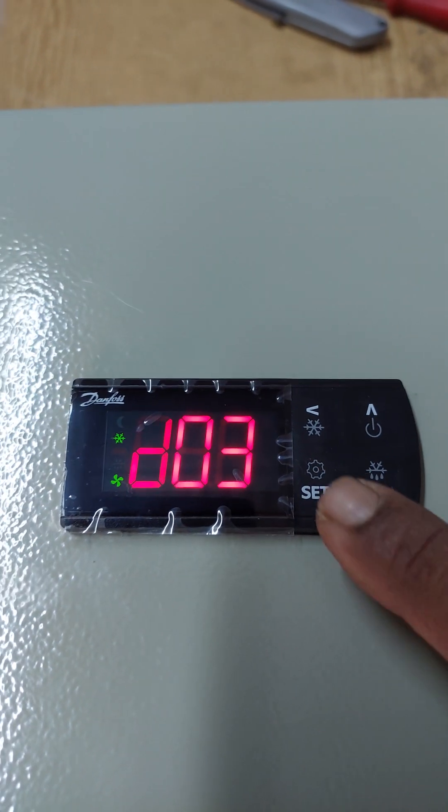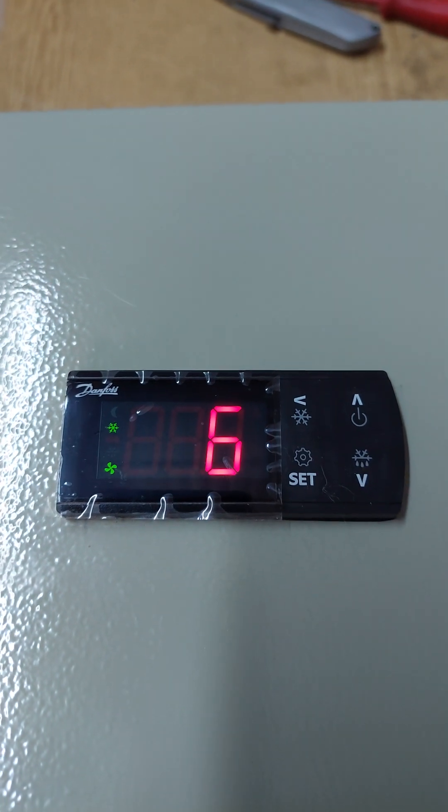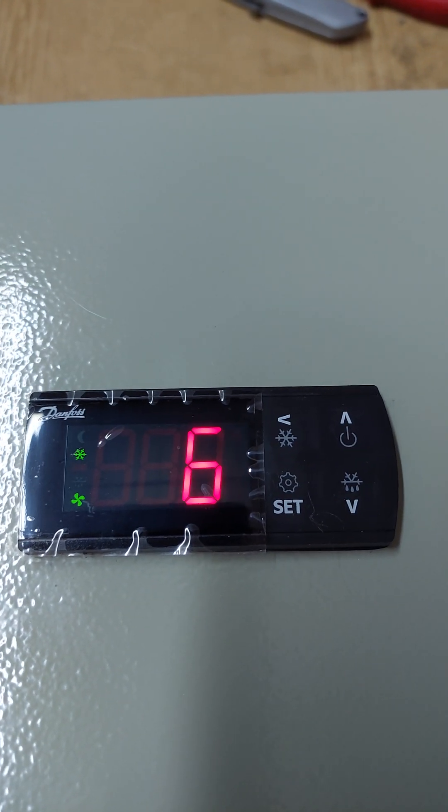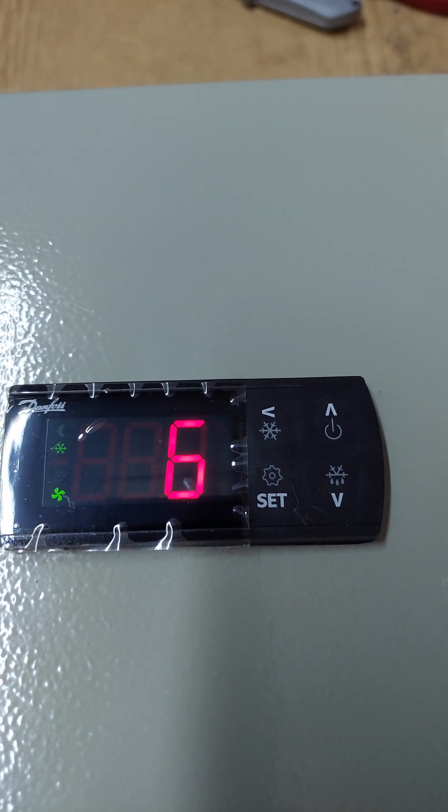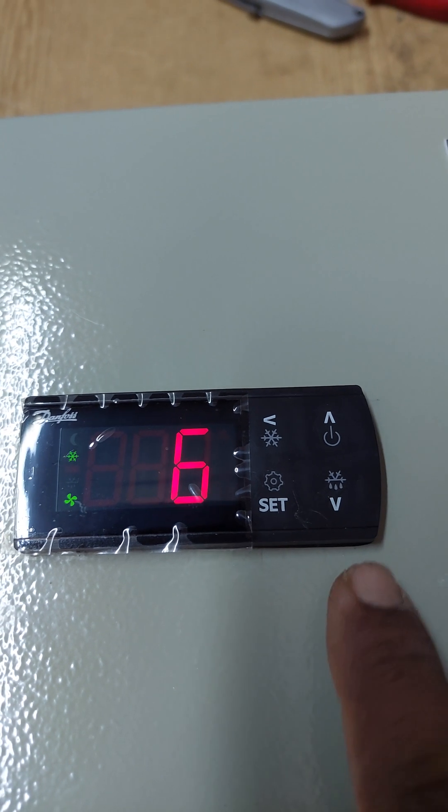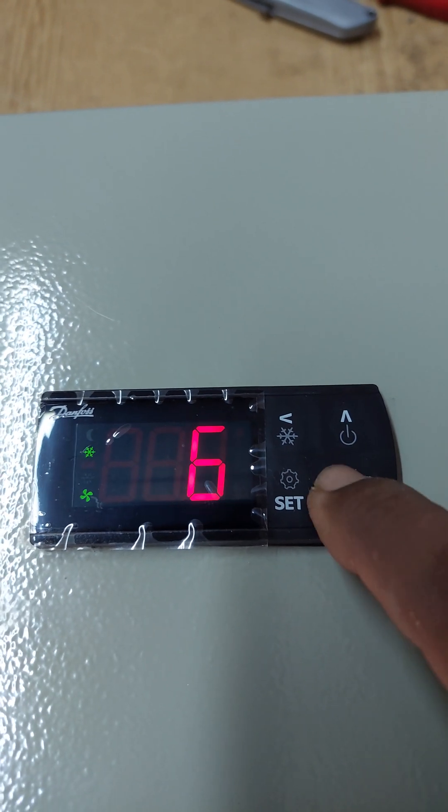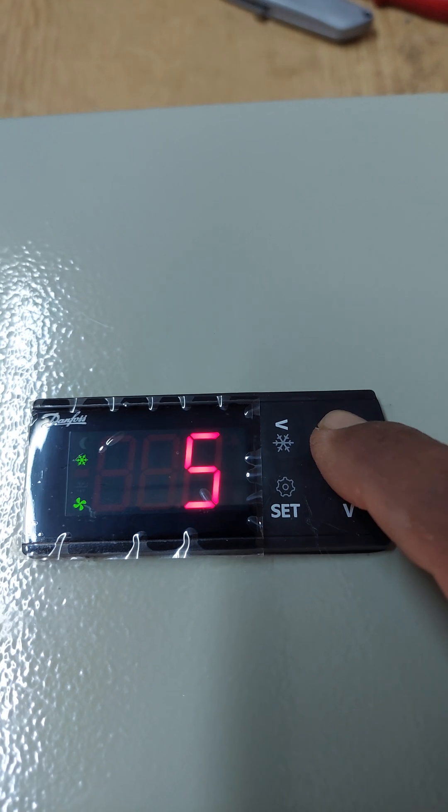Zero three is the interval between defrost cycles. Set it to six hours. You can change the time to five hours, four hours, or other values.